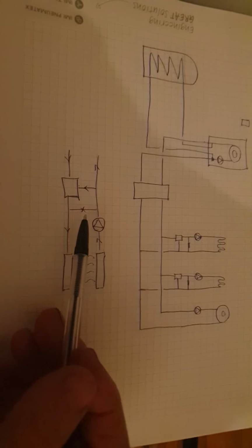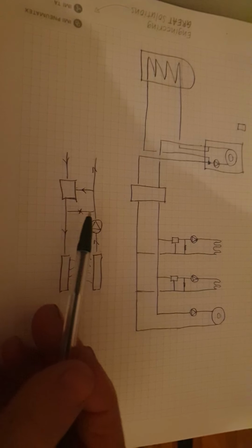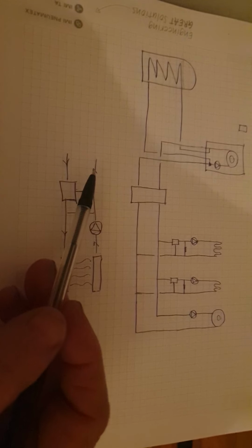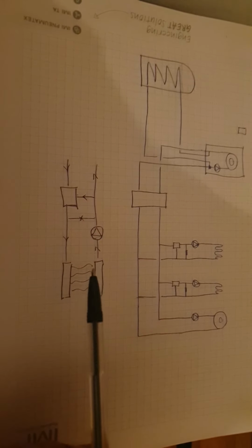And what this does, by allowing some of the flow to be recirculating through this system, is that we don't need to draw high flow rates in from the external system. But this works well with Vstream because the mixing valve is sending a signal back to the boiler, which controls the temperature being supplied into the low loss header. So if we require a higher temperature to be achieved by this mixed water through this fixed rate bypass, the Vstream boiler can compensate for all of this and provide the correct mix.